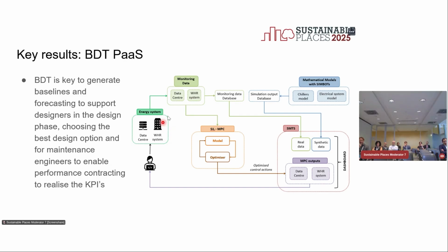From this physical model we collect monitoring data, which goes to a database and is also used in a software-in-the-loop approach. In this software-in-the-loop setup we have an MPC, a model predictive controller algorithm, to optimize the control trajectory of the overall system, both the data center and the waste heat recovery system.